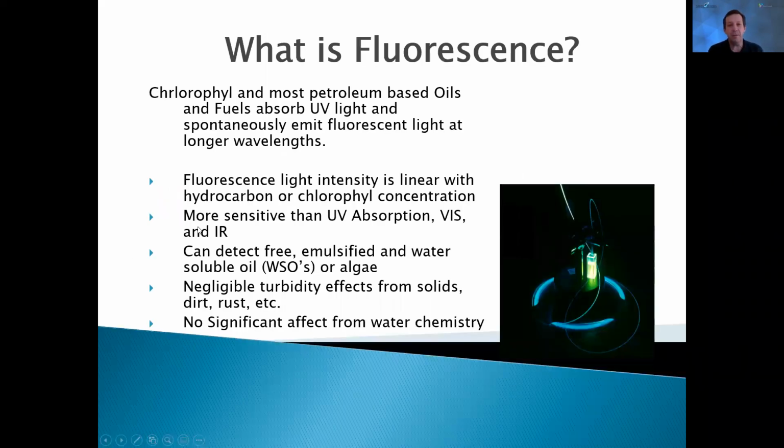So a little bit on our technology. All of our products use fluorescence measurement to measure the constituent that we're looking for. I mentioned that we focus primarily on oil, so we will be talking about oil quite a lot in this presentation. All of the details as far as oil measurement also are true for measurement of chlorophyll, which is a primary component within algae. The only difference as far as a measurement standpoint is the type of light source used in the measurement. All the other details are the same.